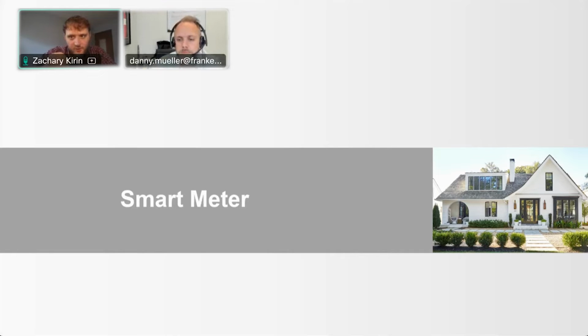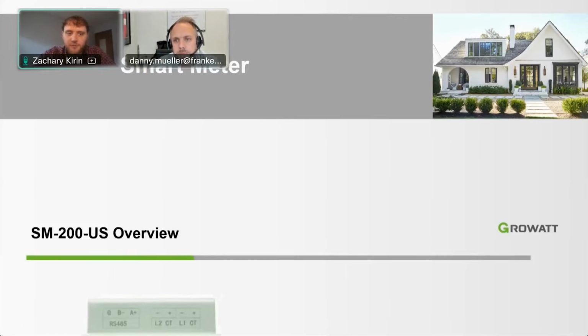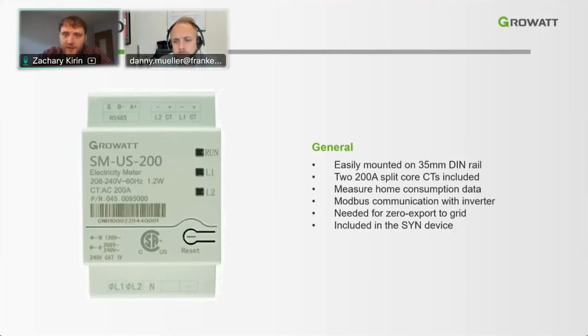Okay, so then on to the Growatt smart meter. These are just a few slides about the smart meter installation. This is an easily mounted 35 millimeter DIN rail ready smart meter, which comes with 2 split core 200 amp CTs. This is mainly made to measure the home consumption data, and it's also required for 0 export limitations to the grid. So this is important for certain municipalities that may not allow any feed into the grid.